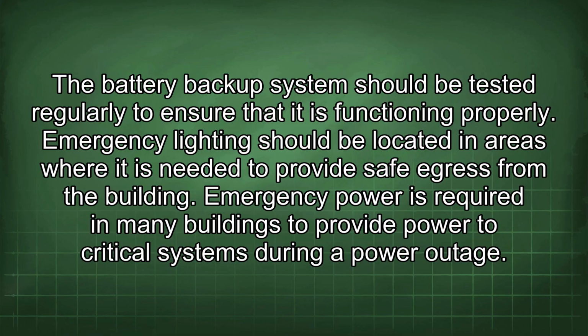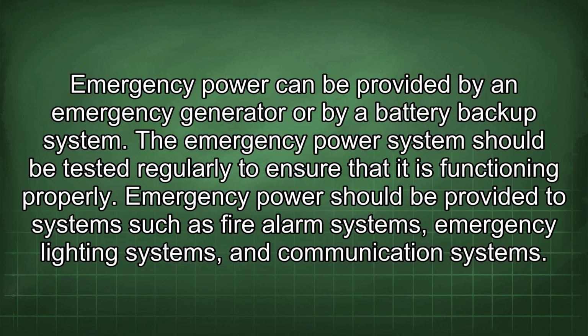Emergency power is required in many buildings to provide power to critical systems during a power outage. Emergency power can be provided by an emergency generator or by a battery backup system. The emergency power system should be tested regularly to ensure that it is functioning properly. Emergency power should be provided to systems such as fire alarm systems, emergency lighting systems, and communication systems.